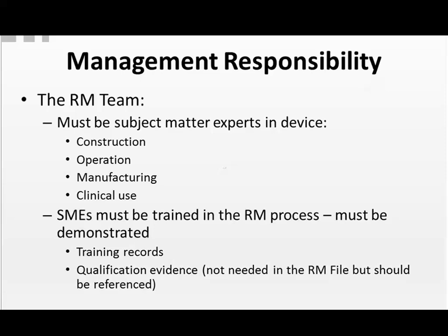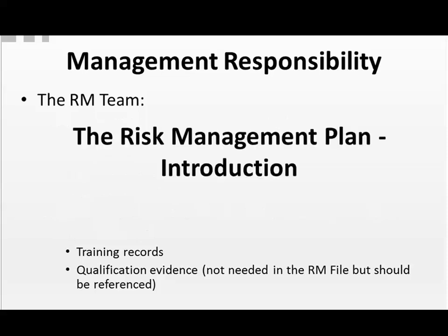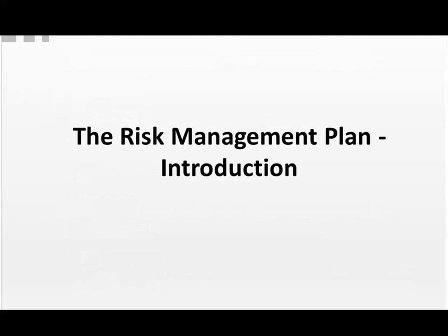Team members must be subject matter experts with a device from the standpoint of construction, operation, manufacturing, and clinical use. They also must be trained in the risk management process, with that expertise being demonstrated through training records and qualification evidence. The expertise possessed by subject matter experts is critical to an effective risk management process. You need that level of skill and knowledge. Now, the center of the risk management process is, as I said, the risk management plan.